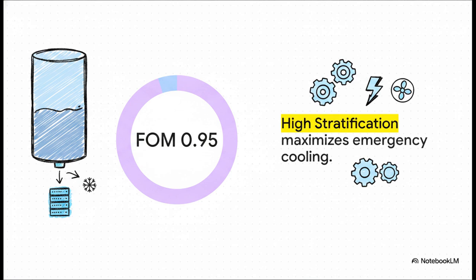Engineers measure this efficiency using something called the figure of merit, or FOM. In a highly stratified tank, the FOM is between 0.85 and 0.95. This means that because the thermocline is so incredibly stable, a staggering 95% of the total water volume can be effectively used to cool the data center during the power failure. The boundary layer is tight, the cold water is pure, and literally almost zero space is wasted.